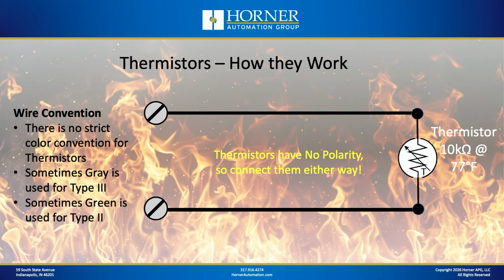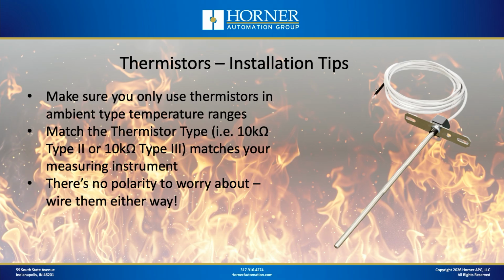Connect them either way, they'll work just fine. Now, some manufacturers that are reputable will use a gray color for the wire leads for type 3, and they'll use green color for the wire leads for type 2. And that would define the color of both wire leads, because again, it doesn't matter which way you connect them. In terms of installation tips with thermistors, they're extremely simple to deal with. You just need to make sure that if you're going to be using a thermistor, that you're talking about a temperature range that is appropriate for that type of sensor. You're going to want to make sure that if your measuring instrument supports only type 2 or only type 3, that you're going to use the appropriate thermistor type when you purchase your instrument. And again, you don't need to worry about polarity, which makes them extremely easy to deal with.